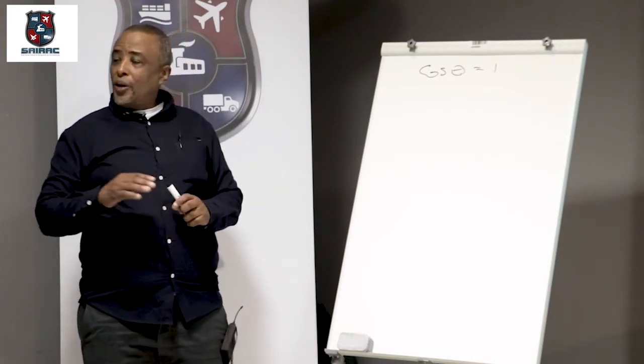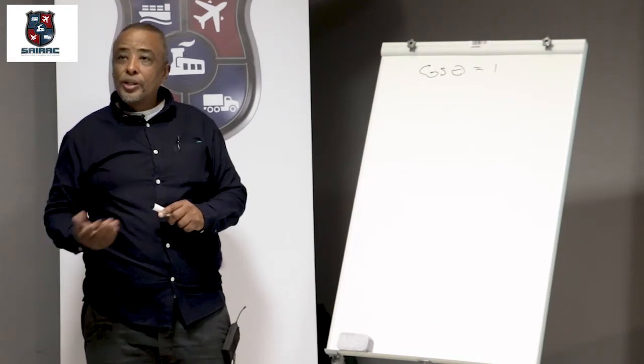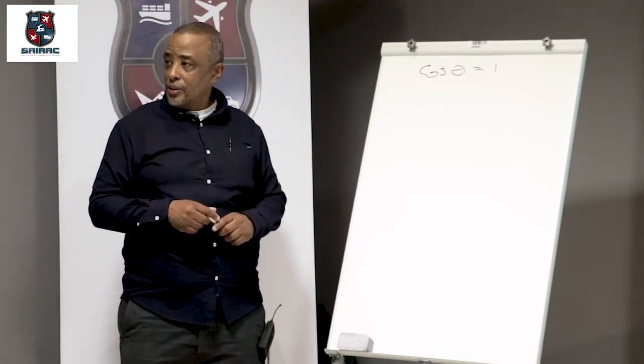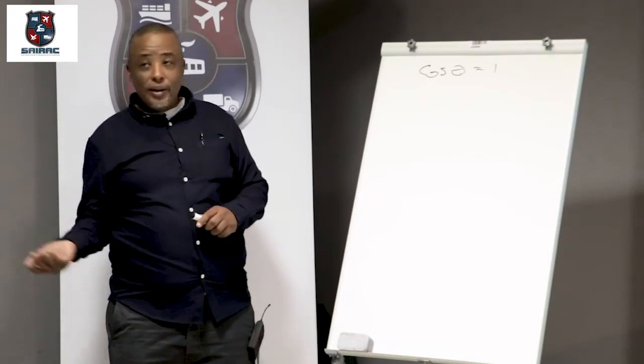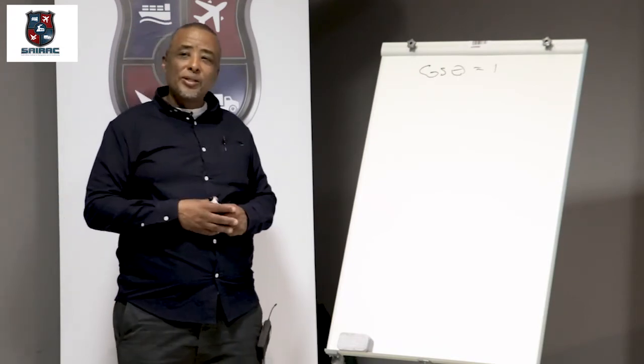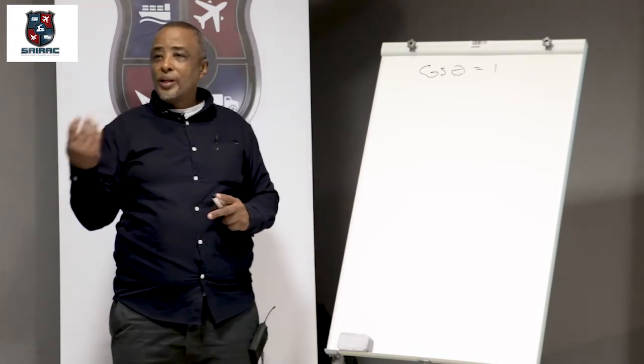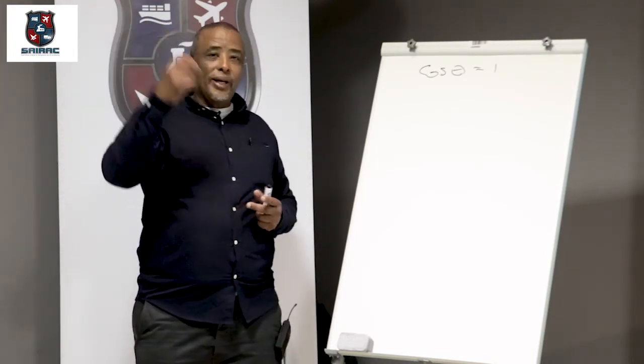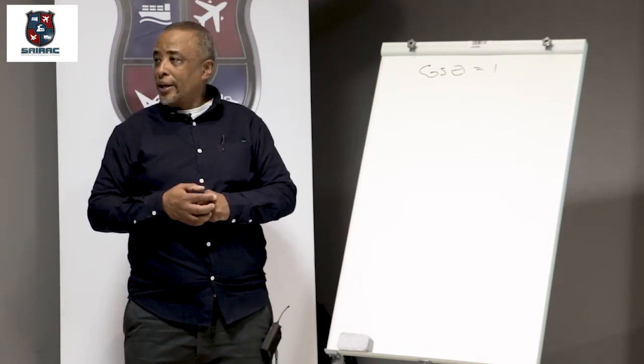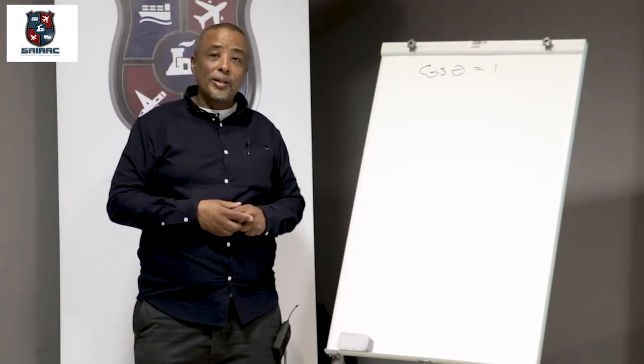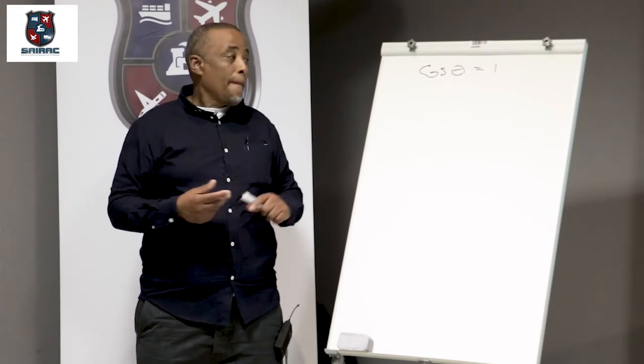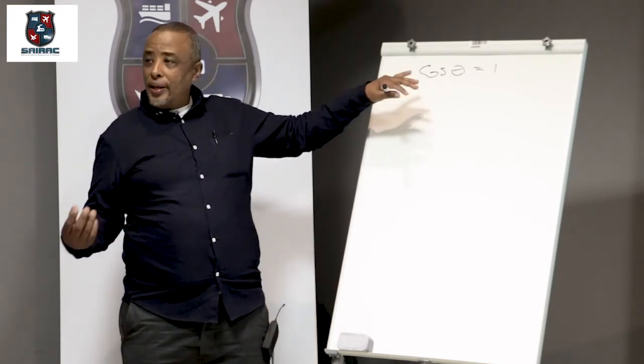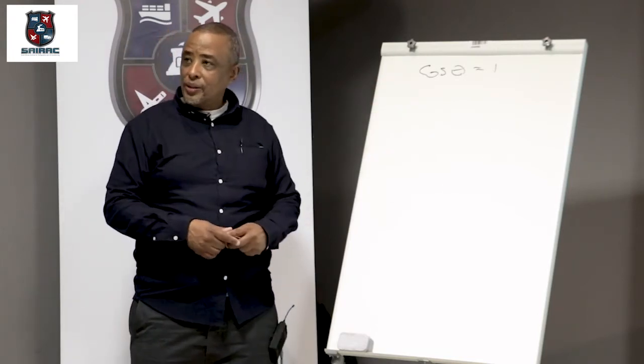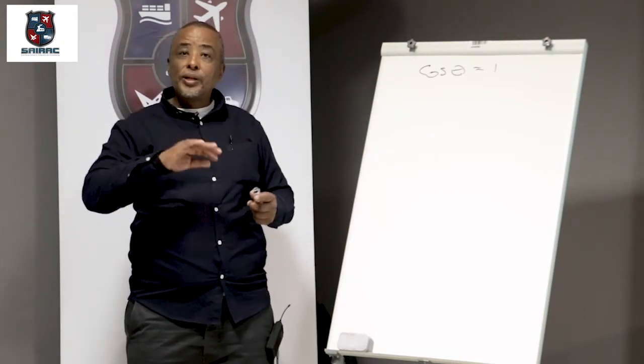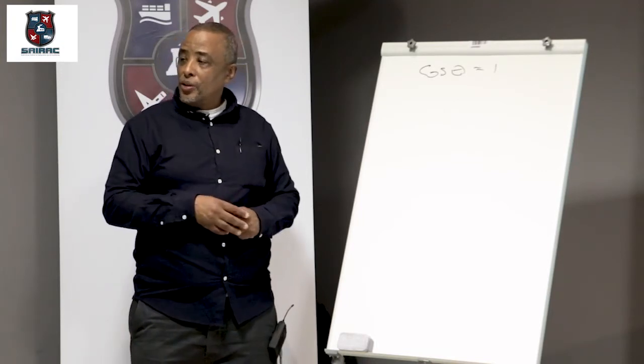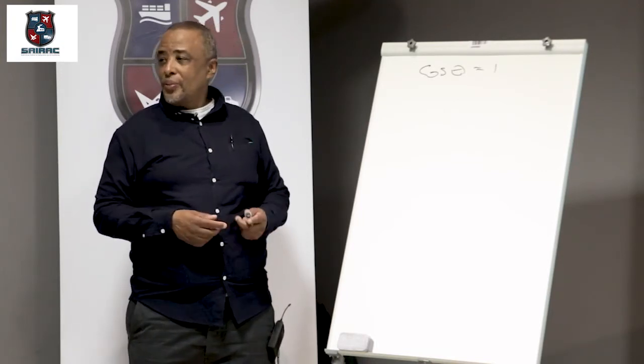Okay. If you find your power factor maybe is lagging too much and you need to improve on it, you can add capacitors. And then it could be the other way around. Generally in factories we have motors, just about in everything. Now it's changed a bit because we've got LED lights, but in those days they were fluorescent lights. Heavy inductive loads. And the heavy inductive loads do cause a lagging power factor. So we need to put in capacitors to compensate, to try and get our power factor closer to unity. Calculation of it can be done, maybe for another day.